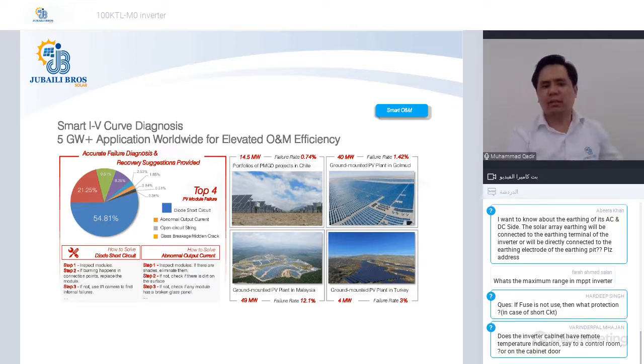So this has been implemented in many different projects around the globe. A few scenarios are in front of your screen. There is a case of Chile where there is a 14 megawatt PV plant and Huawei has found a 0.74% failure rate due to different issues with the PV strings. When Huawei gives you this IV curve diagnosis report in the shape of a PDF, you will get the IV curve of each PV string, and at the end, you will also find a table which shows, against each of the issues, what remedies you can apply in order to solve the issues in the PV string.